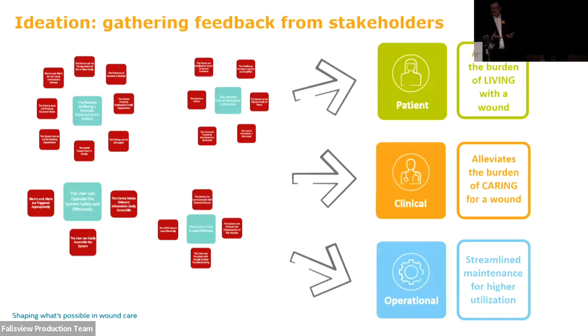So what would a design input be? It could be to satisfy the patient that we're alleviating the burden of living with the wound. So that could be portability of the device. It could be quietness, discretion. It could be the odor management. It could be that the alarms are appropriate and not false alarming. So those kind of high-level design inputs are testable.